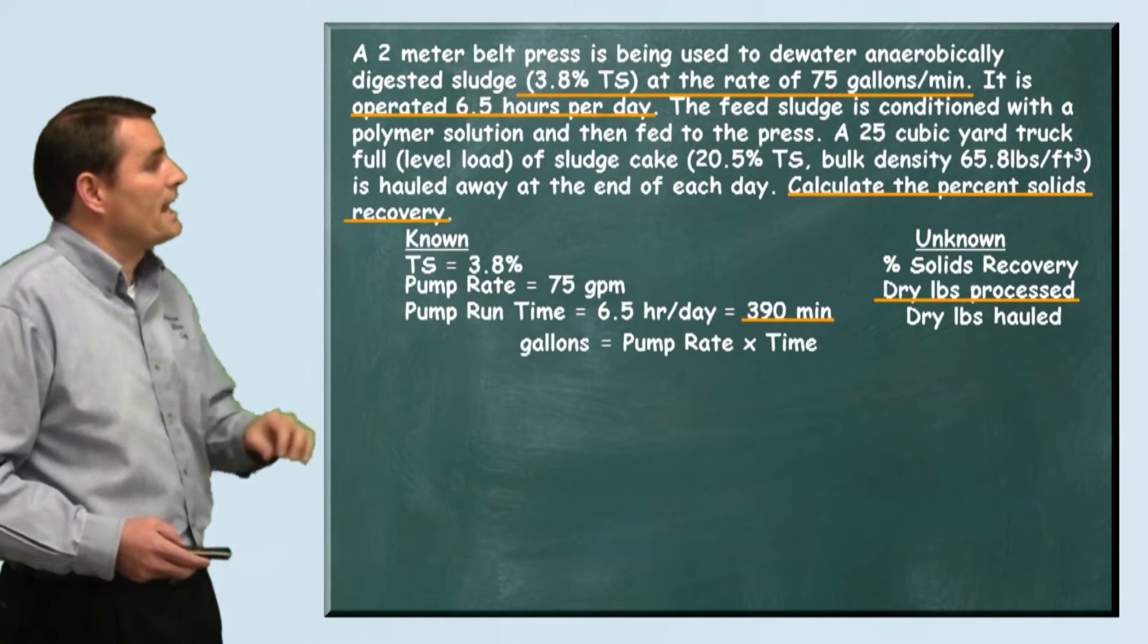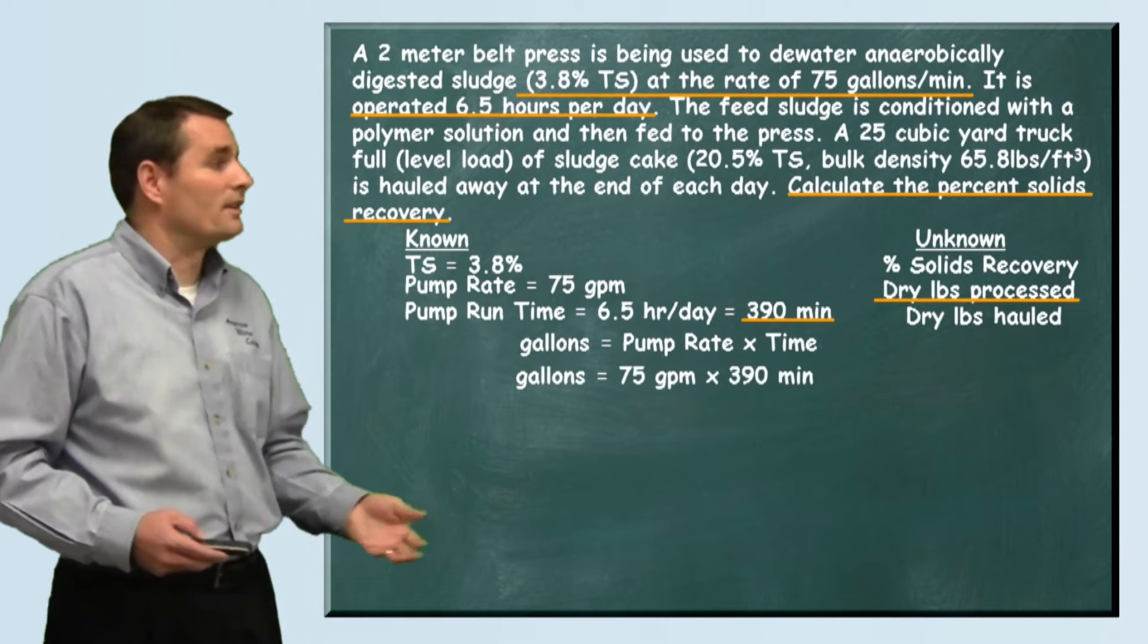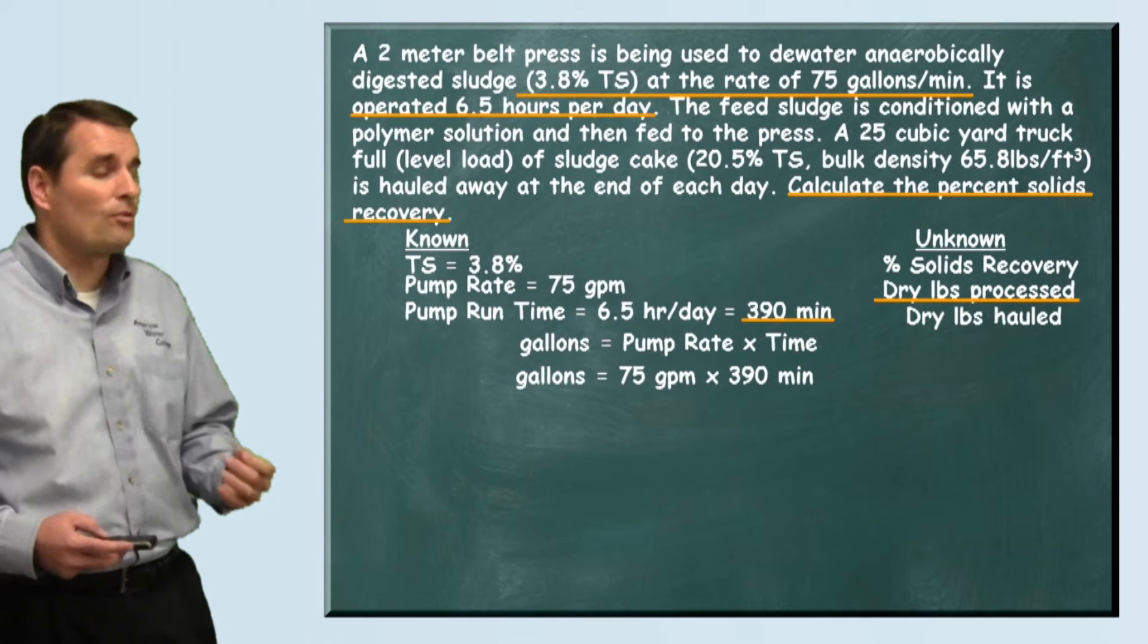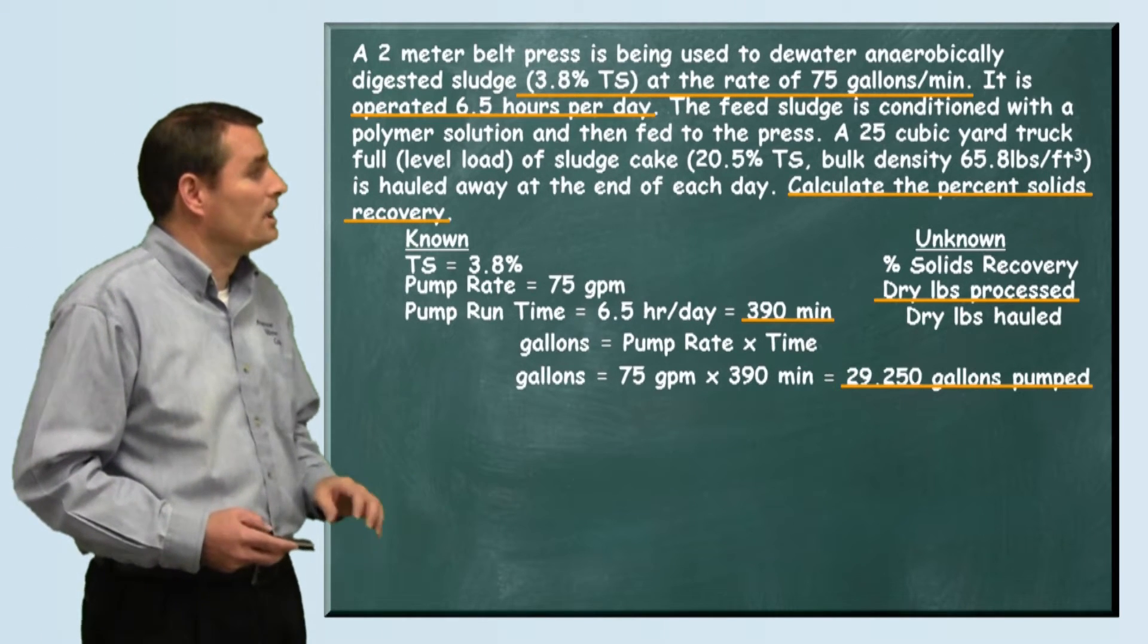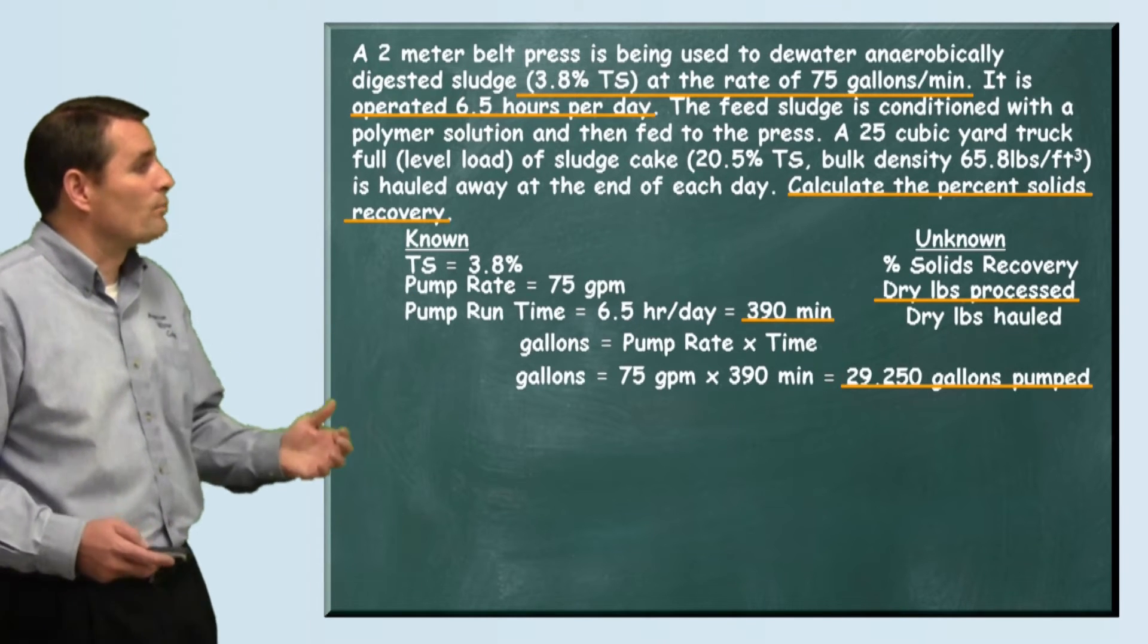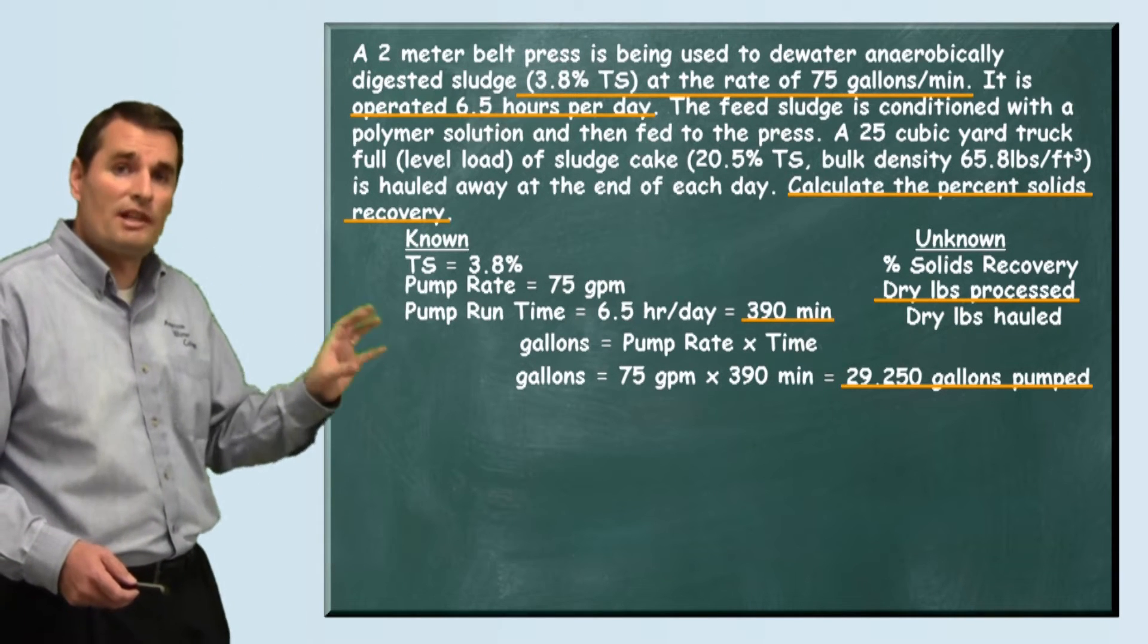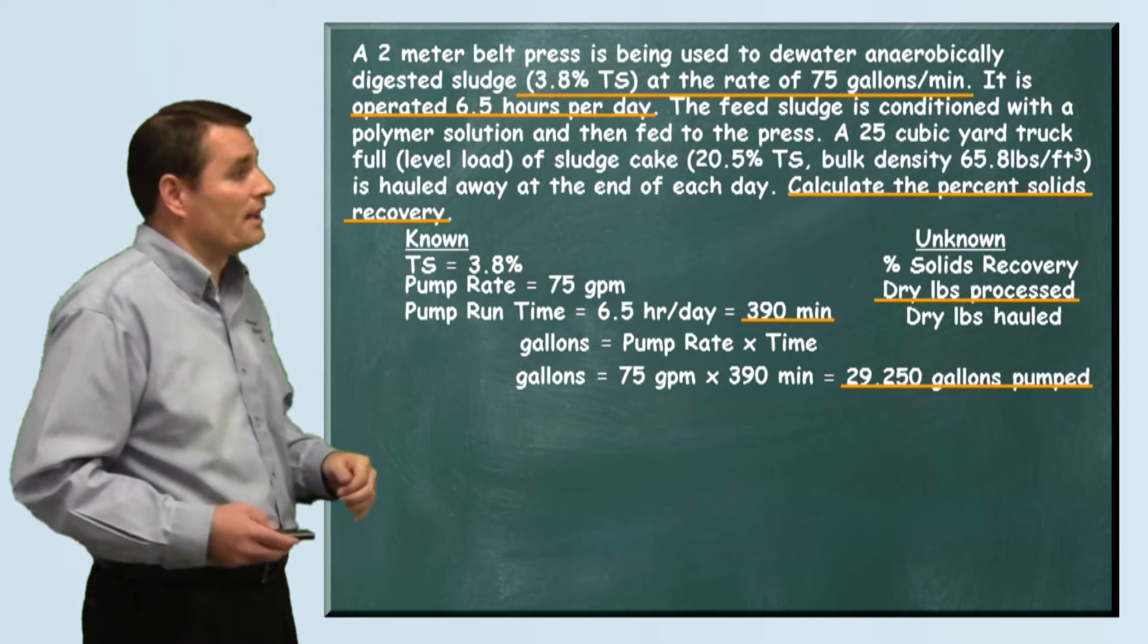To find our total gallons of sludge pumped, we're going to multiply our pumping rate times the time. We plug in our 75 gallons per minute and multiply it by the 390 minutes per day that that pump runs. We see that during this day we process 29,250 gallons. That's how much sludge goes to the belt press to be processed.